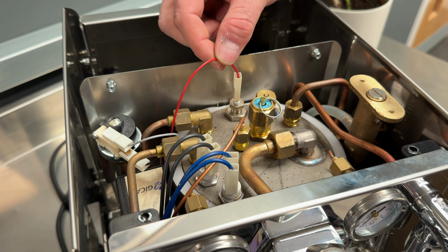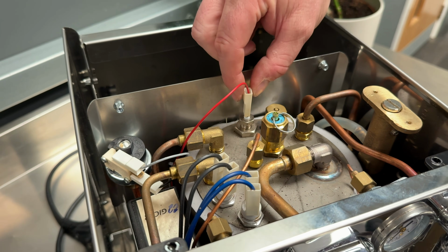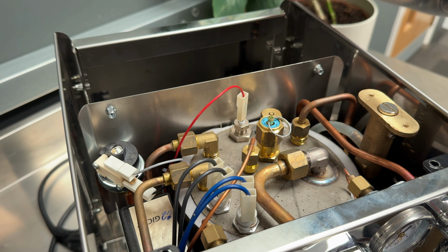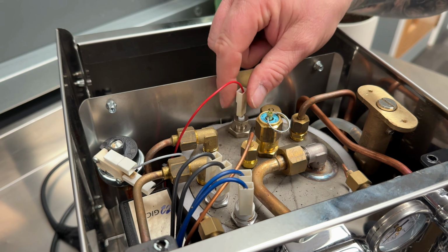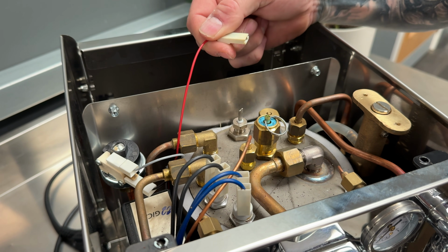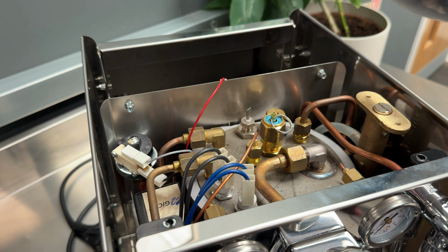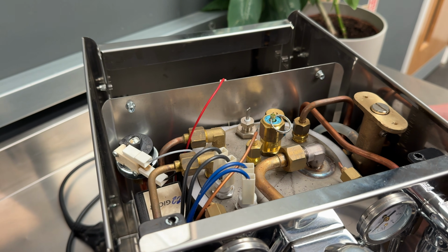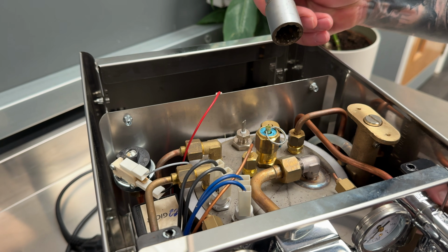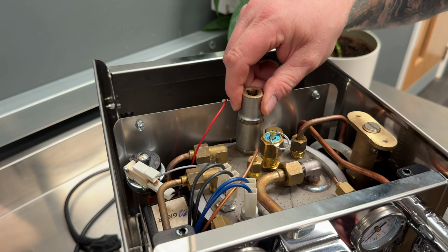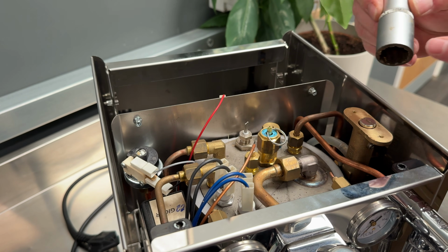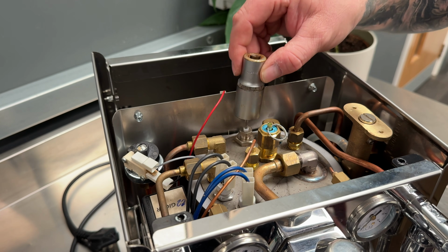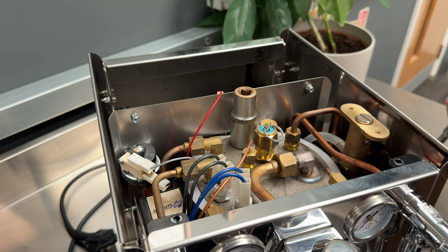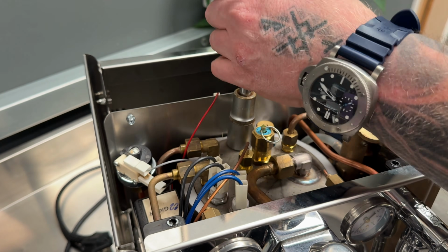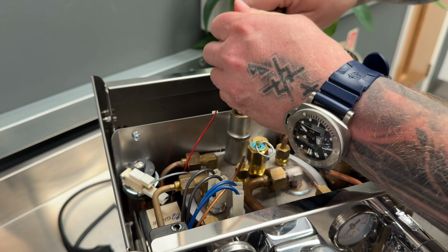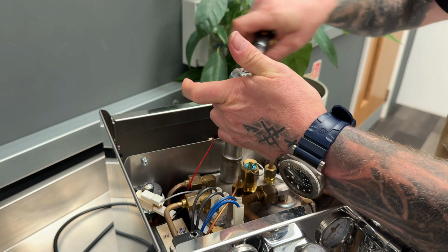So this here, the single wire, is your water sensor probe. All you need to do is disconnect the supply, and then you will need a 19mm socket, and in this case a deep socket, just to allow for the height of the probe there. So pop the socket on there and then simply undo anti-clockwise.